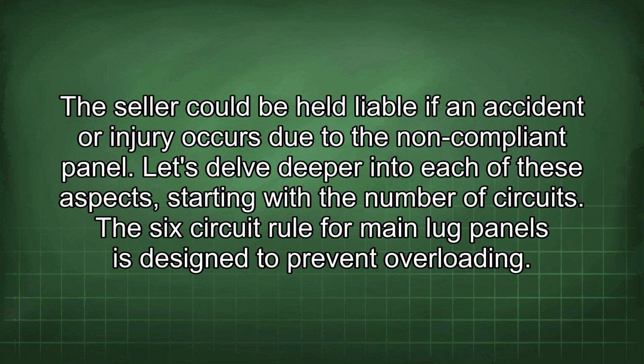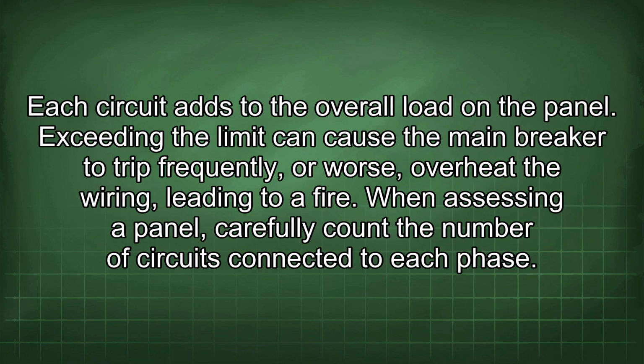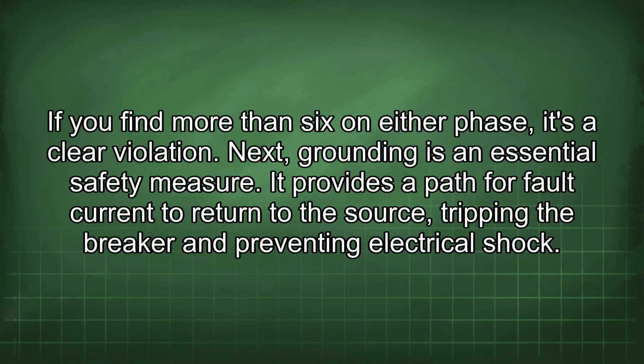Let's delve deeper into each of these aspects, starting with the number of circuits. The 6-circuit rule for main lug panels is designed to prevent overloading. Each circuit adds to the overall load on the panel. Exceeding the limit can cause the main breaker to trip frequently, or worse, overheat the wiring, leading to a fire. When assessing a panel, carefully count the number of circuits connected to each phase. If you find more than 6 on either phase, it's a clear violation.